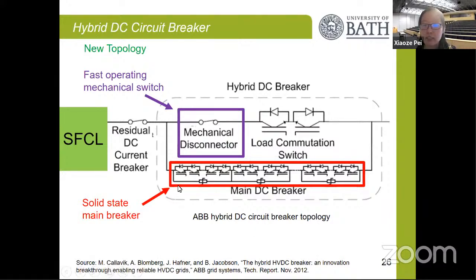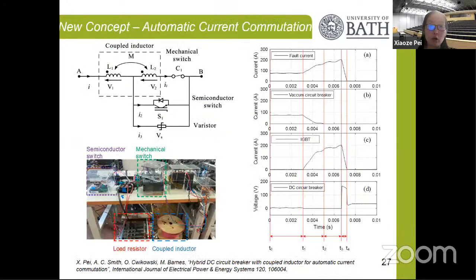Thirdly, we also look at the design of the solid state DC circuit breaker, because with a higher voltage and current level, we will need series connection of the semiconductor devices. What is the current balance and the voltage balance in the system? With a new concept, we proposed an automatic current commutation circuit, which basically uses a coupled inductor in the system. When a fault current happens in the main circuit, because those 2 inductors are coupled together, it produces a voltage that automatically drives the current out of the mechanical switch and commutates it to the semiconductor switch. We have already built one demonstrator in the lab.